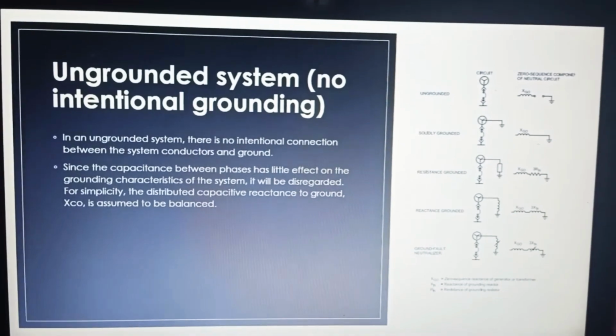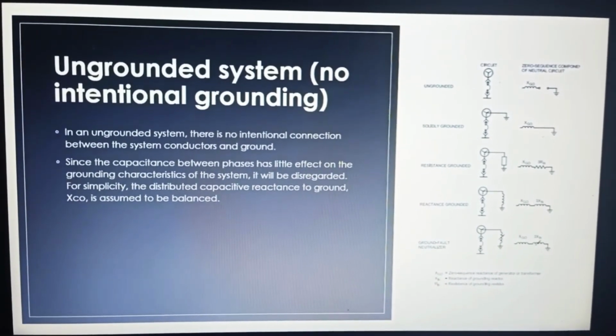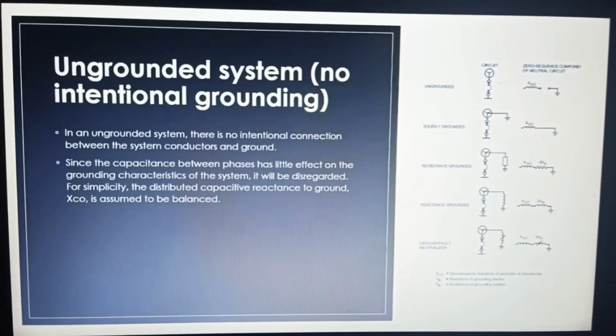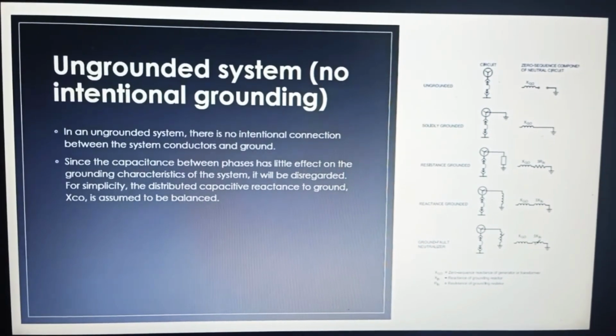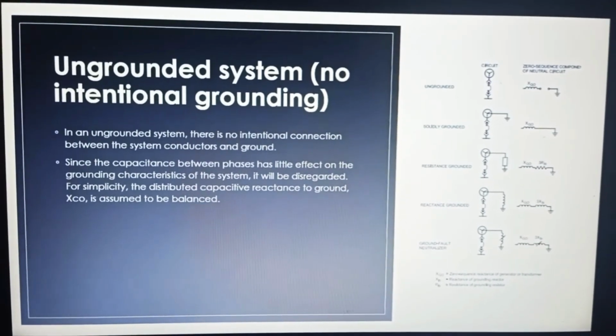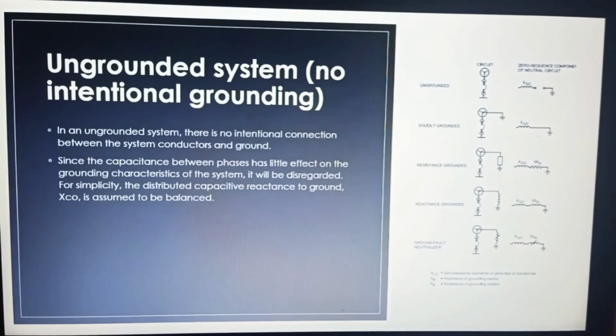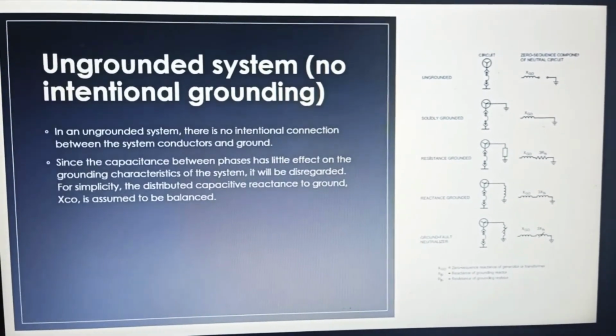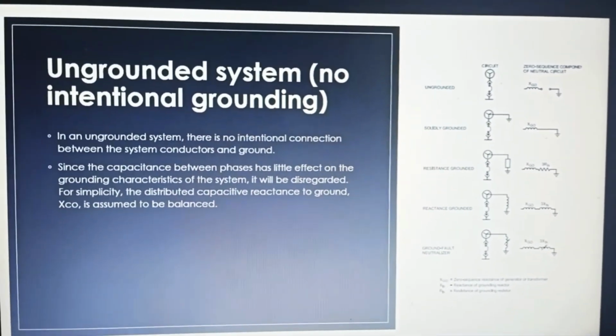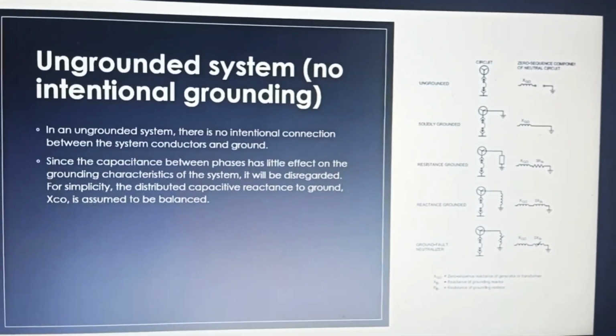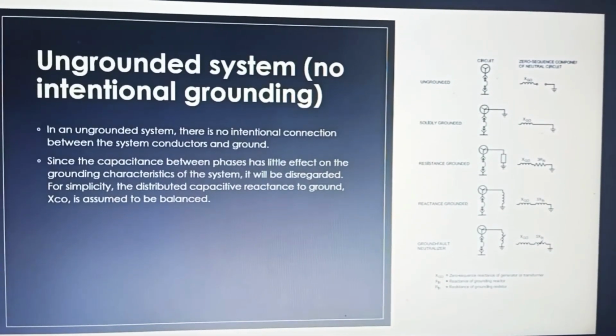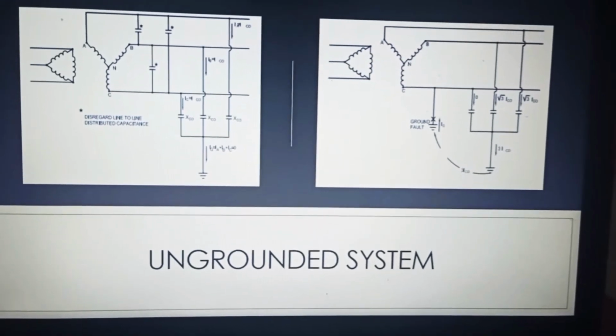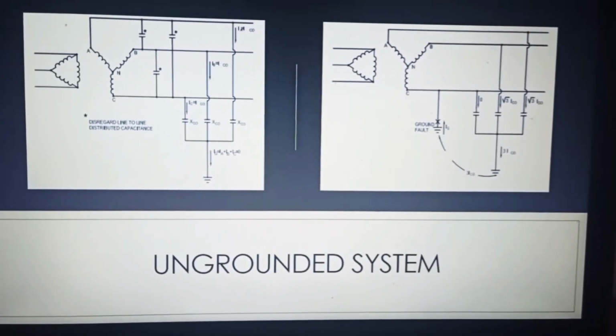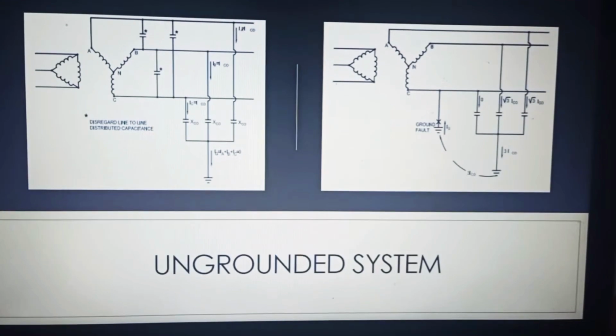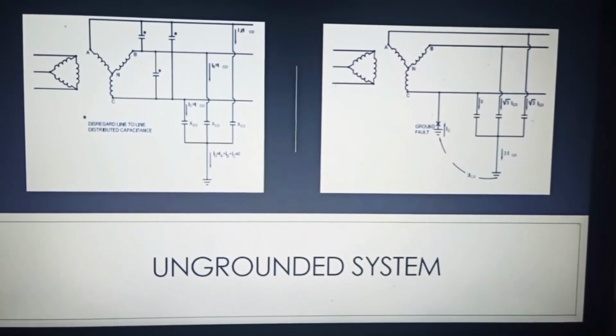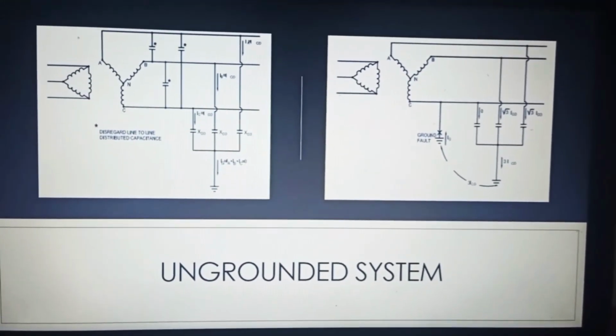Experience has proven that this overvoltage may cause failure in insulation at multiple locations in the system, particularly at motors. Transient overvoltage from restriking ground faults is the main reason why ungrounded systems are no longer recommended, and grounded systems of some form are the predominant choice. To reduce the transient overvoltage during restriking ground faults, one should ground the system using either solid or impedance grounding, as indicated in this picture.